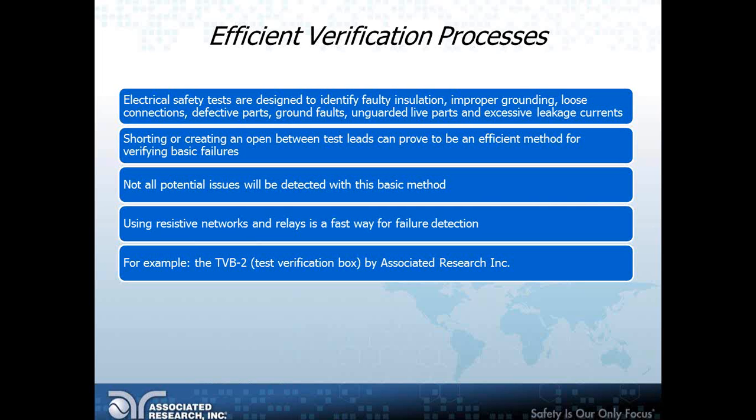But what we're going to lay out for you in this webinar are some basic means of verifying your electrical safety tester and seeing that it's measuring the correct leakage or the correct impedance, etc. Using resistive networks and relays is basically a quick and fast way of detecting if a tester is failing properly, or detecting failures and passes properly.